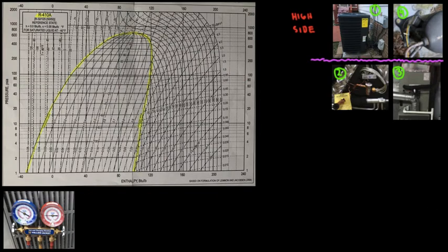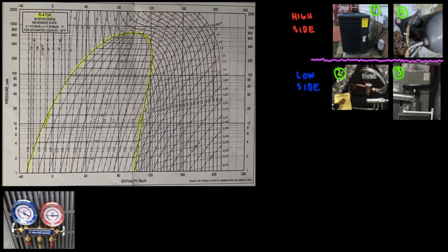The other side is blue, and we call that the low side. The low side is related to the evaporator — low pressure and low temperature — because the TXV makes sure of that. So the condenser and compressor are at high pressure and high temperature, while the evaporator side is at low pressure and low temperature. The blue gauge tells you the pressure and temperature of the evaporator, and the red gauge tells you the pressure and temperature of the condenser.